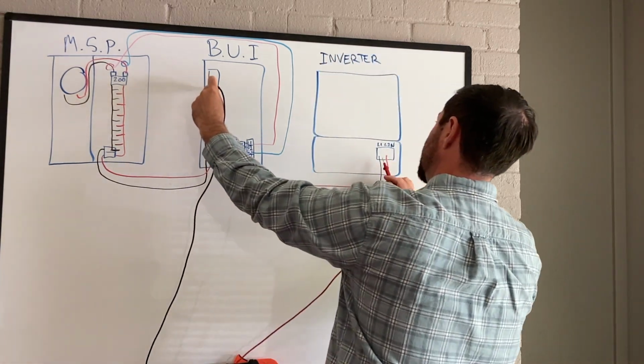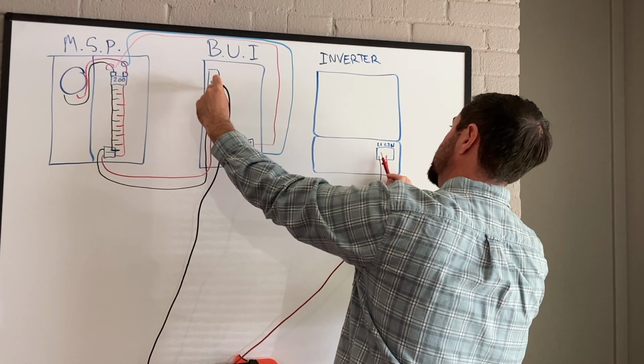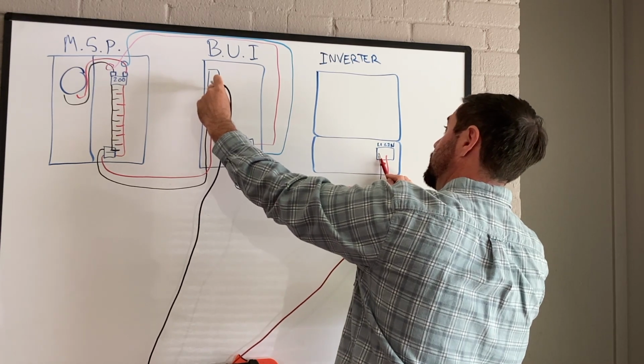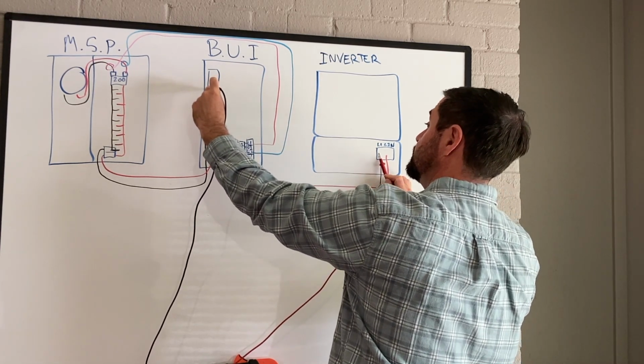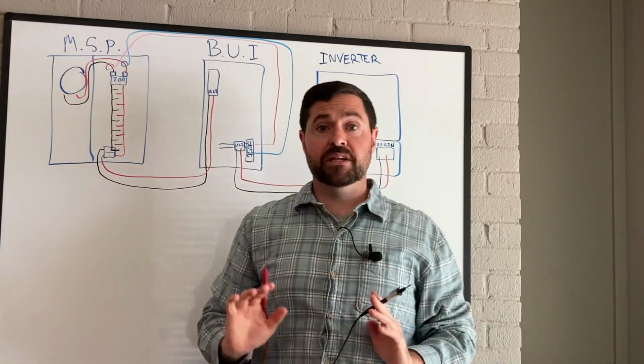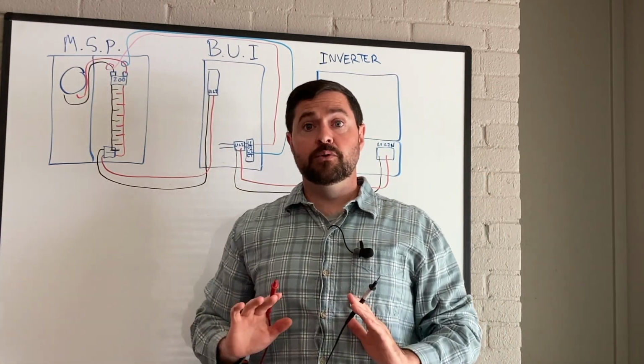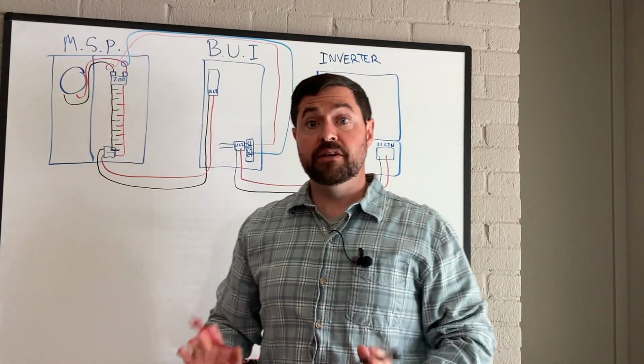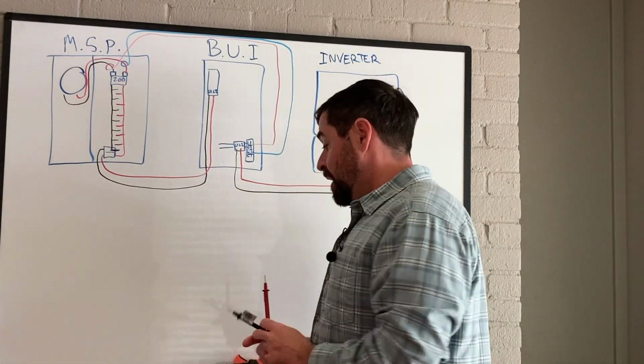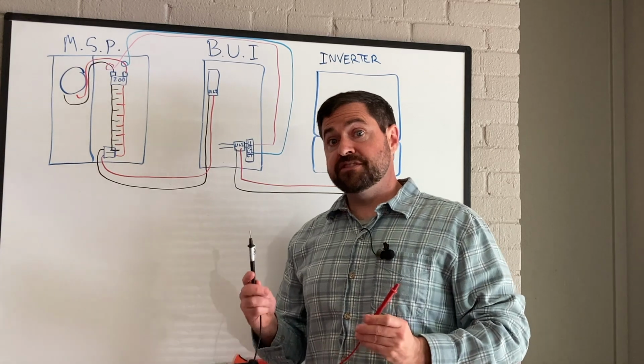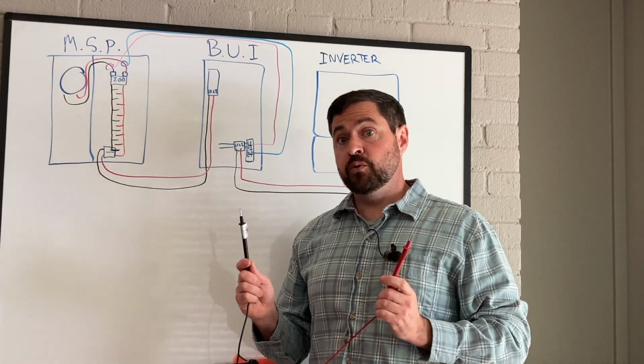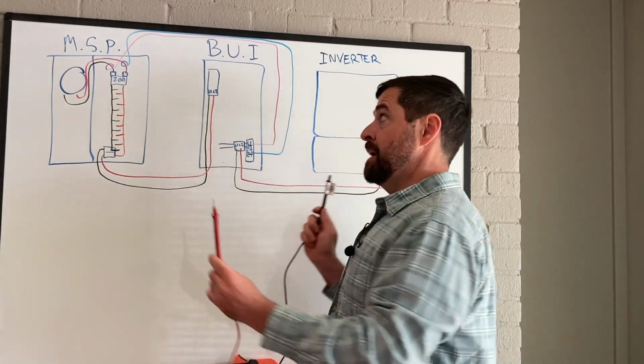Lastly, we check that to the L1 lug going into the solar inverter. We want to see 0 volts. If at any point we get 240 volts, you have crossed phases somewhere and you need to fix it. Now, another common issue that you're going to see is when you do this, maybe you can't reach.